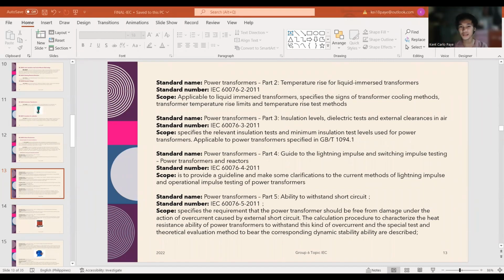The next parameter standard is the guide to the lightning impulse and switching impulse testing of power transformers and reactors. This standard provides a guideline and makes some clarifications to the current methods of lightning impulse and switching impulse testing of power transformers. Then the next parameter standard is the ability to withstand short circuits. This standard specifies the requirement that the power transformer should be free from damage under the action of overcurrent caused by an external short circuit, the calculation procedure to characterize the heat resistance ability of the power transformer to withstand this kind of overcurrent, and the special test and theoretical evaluation method for the corresponding dynamic stability ability.